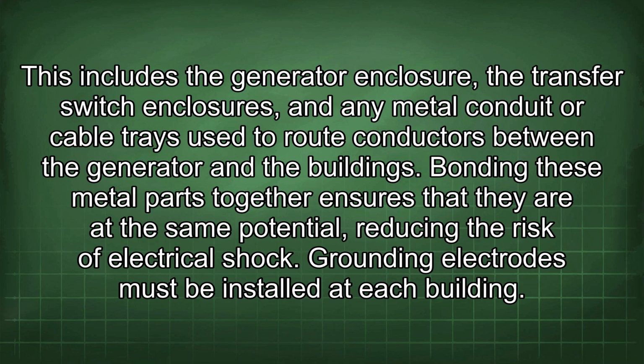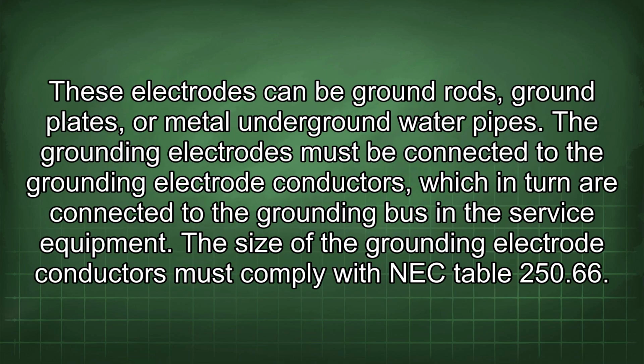Bonding these metal parts together ensures that they are at the same potential, reducing the risk of electrical shock. Grounding electrodes must be installed at each building. These electrodes can be ground rods, ground plates, or metal underground water pipes.